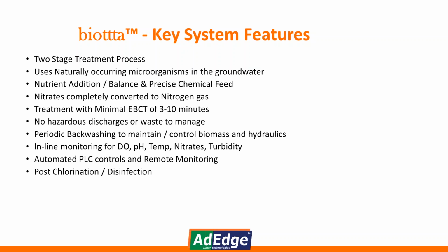In the system, we have nutrient additions that we carefully control through integration to instrumentation. We convert all the nitrates to nitrogen gas and water. We can actually run at very fast flow rates through the system. If any of you have arsenic treatment systems out there, you'll see this 3 to 10 minute EBCT. And the flow rate through these is very similar to what you would see in a conventional filtration system like that. Again, there's no hazardous discharge or waste to manage.